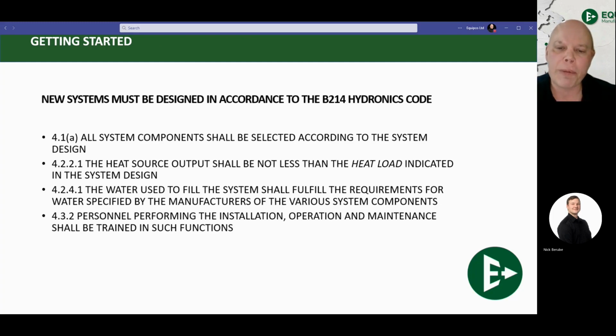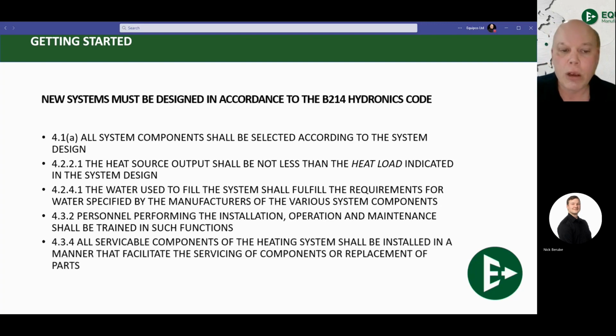432. Personnel performing installation shall be trained in such functions, meaning that if you are a contractor and you're installing this brand of boiler, train yourself in it. Contact the representative, such as Equipco for various lines. We're happy to do trainings to teach you the finer details of installation of various products. This is required by code. It has to be done.